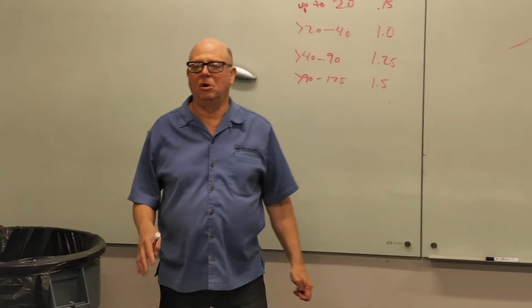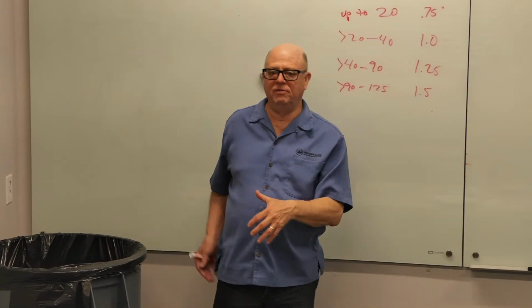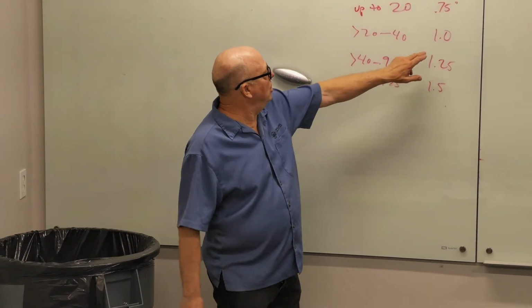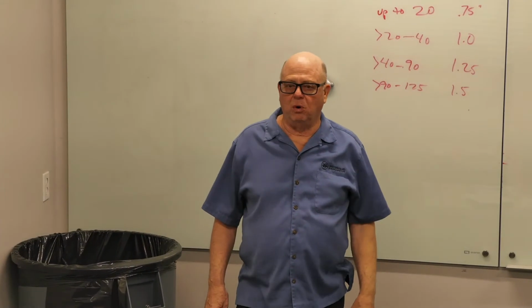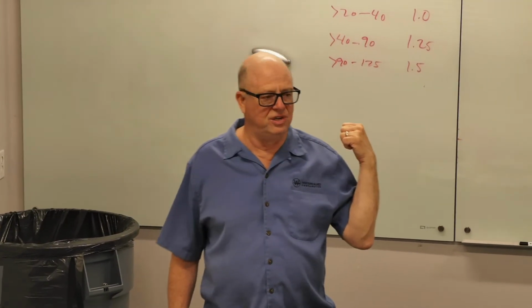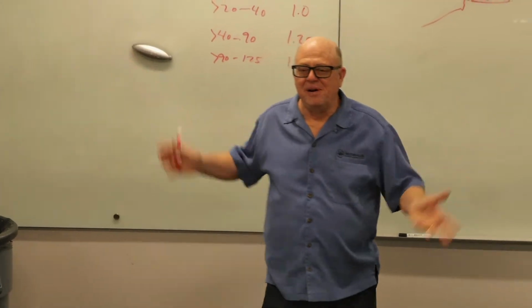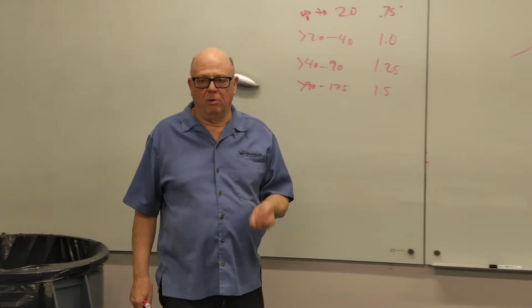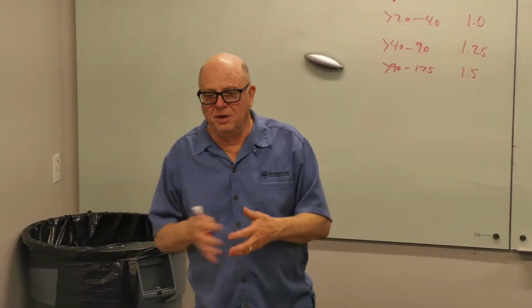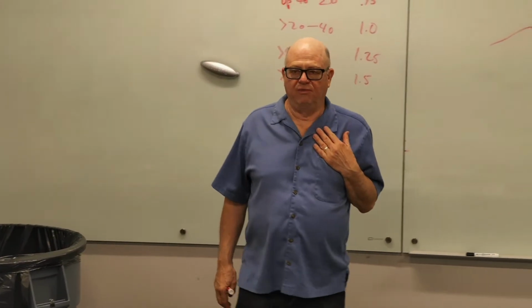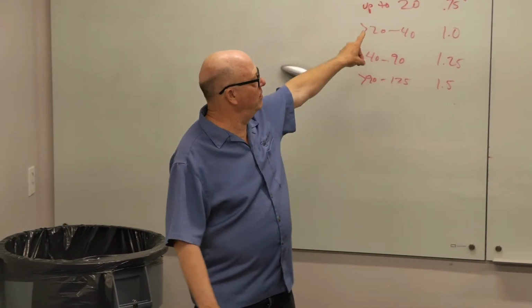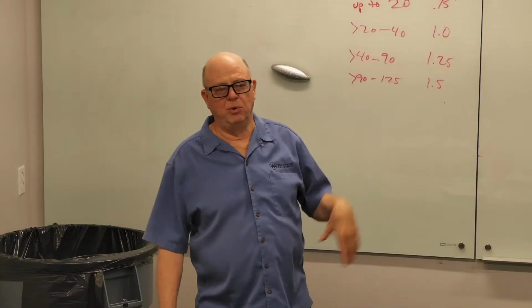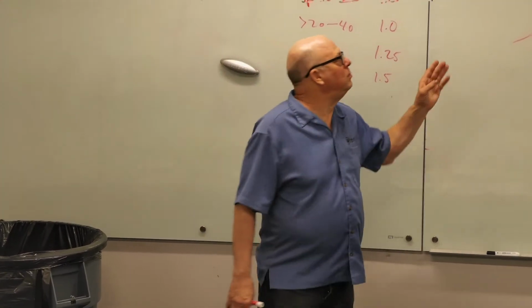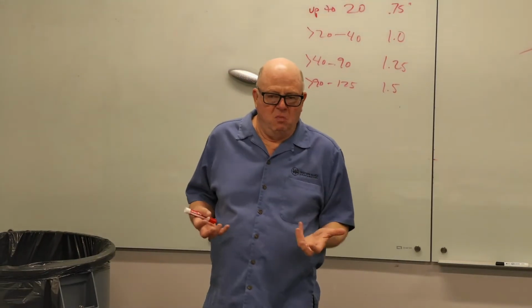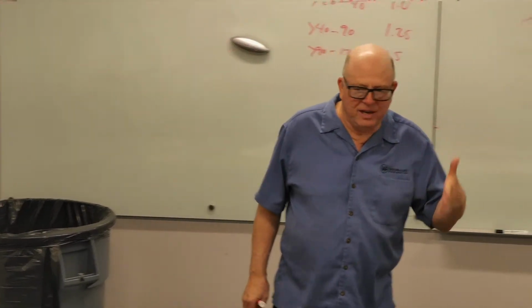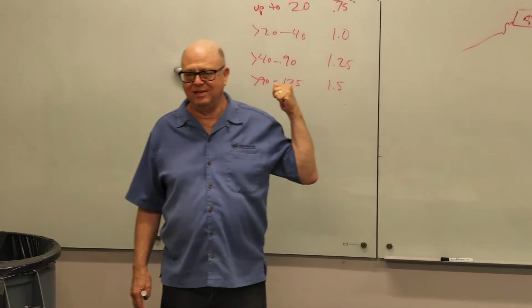Now, code is not brilliant. Code tends to err on the side of being conservative and being safe, right? So do you always need exactly that to make it work? Well, hell, if you're in Death Valley, you'd never have any condensation at all, right? So it would be irrelevant. Code is built around what is a likely worst case humidity scenario, which Southern California never had before. This is Universal Plumbing Code, which is UMC, UPC. So it wasn't a problem. But another statement about how climate has changed is that we started overflowing these lines.